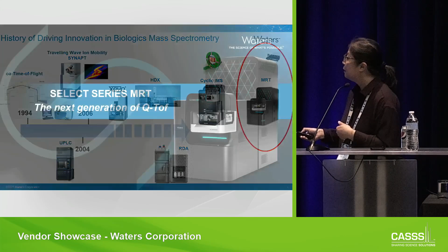Select Series MRT, the next generation of QTOF. This is just to give you an overall performance of what the MRT instrument can do. It is our Waters next generation QTOF instrument. And it can routinely give less than 1 ppm mass accuracy, on average about 500 ppb mass accuracy, which is pretty impressive. And in the MRT mode, you can get 200,000 mass resolution at full width, half maximum. And it's irrespective of your acquisition rate. So your mass resolution does not decrease if you're doing 10 hertz acquisition, 5 hertz, or 2 hertz, or 1 hertz. It stays the same.